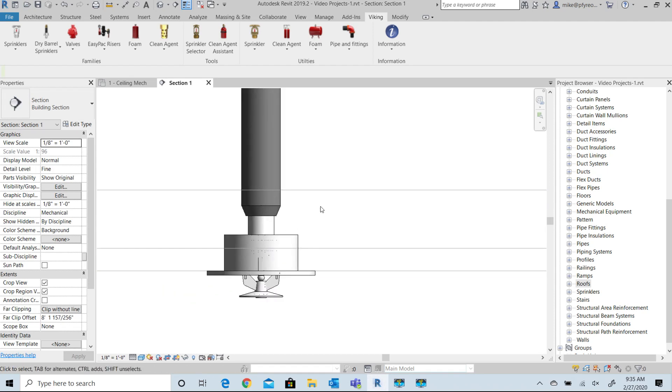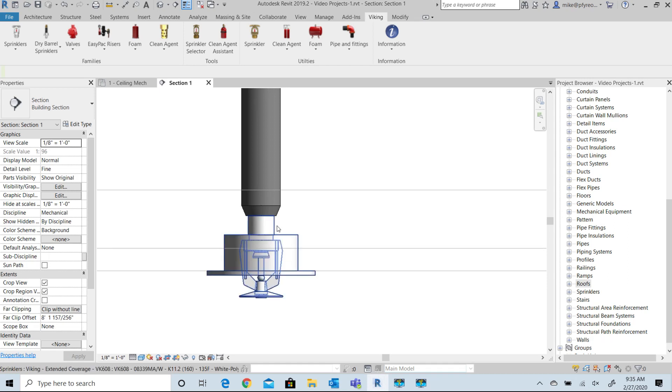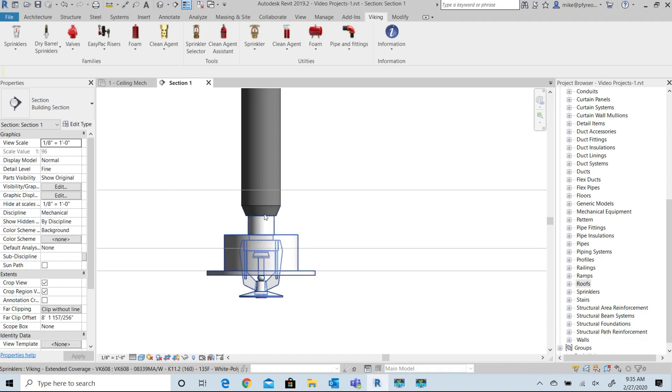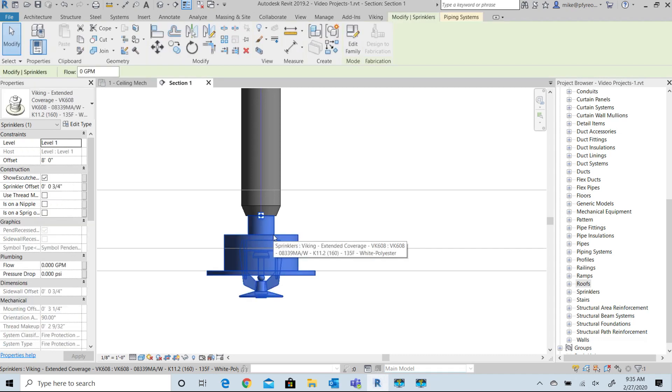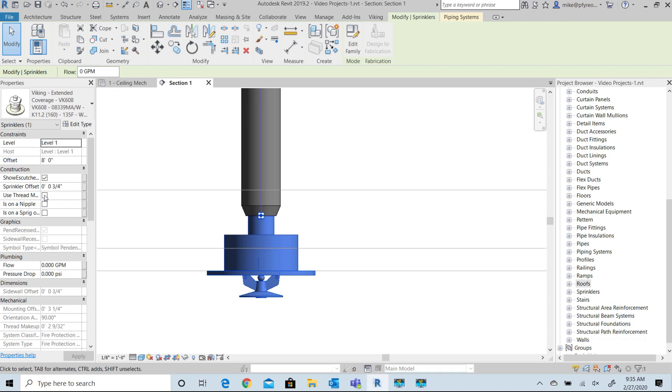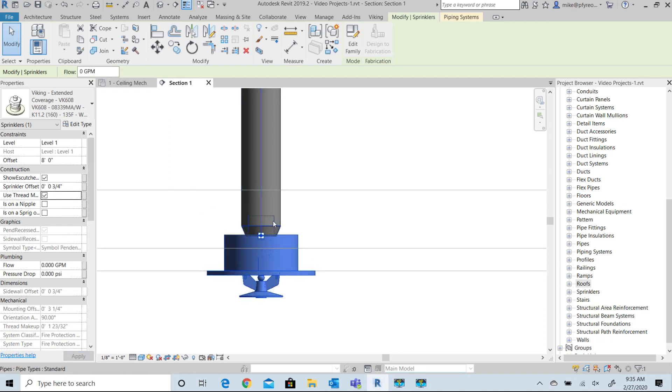If you're using the standard supplied Revit MEP template pipe and fittings, we provide another adjustment option. The pipe connector for the sprinkler is at the end of the sprinkler thread and the connector for the supplied fitting from Revit is the face of the reducing fitting. We provided another option to adjust for the makeup of the sprinkler into the fitting.